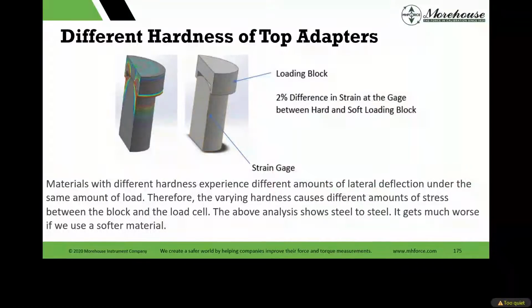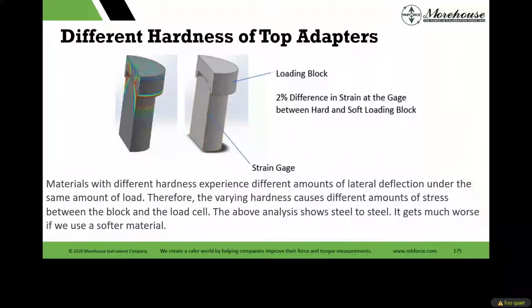So we modeled this. You can model it in SolidWorks. It's modeled in, and you can start seeing the loading block and what impact this has. This modeling shows a 2% difference in the strain of the gauge between the hard and soft loading block, calculated using, as I said, SolidWorks. Materials with different hardness experience different amounts of lateral deflection under the same amount of load. Therefore, the varying hardness causes different amounts of stress between the block and the load cell. So above, we tested steel to steel. It gets much worse if we use softer material.